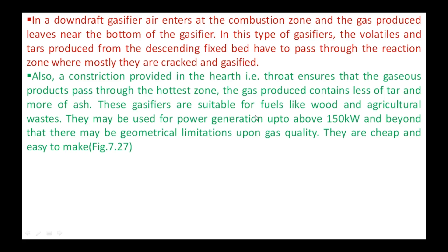The downdraft gasifier is suitable for fuels like wood and agricultural waste. It is mainly used for power generation up to 150 kilowatts; beyond that there may be geometrical limitations on gas quality and gas quantity. These gasifiers are cheap, low cost, and easy to fabricate.